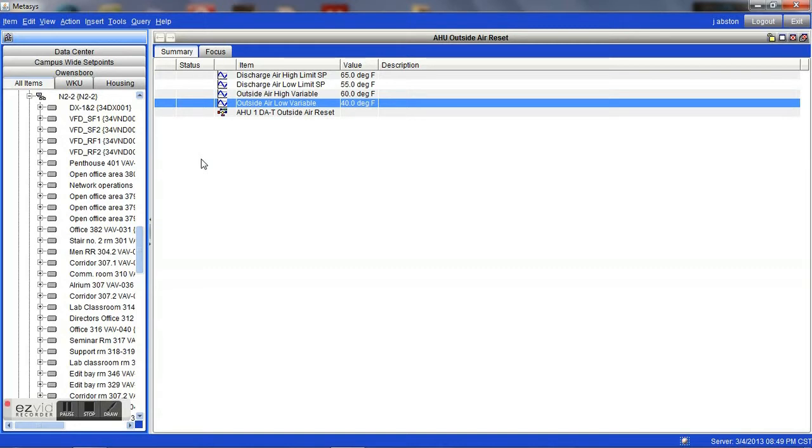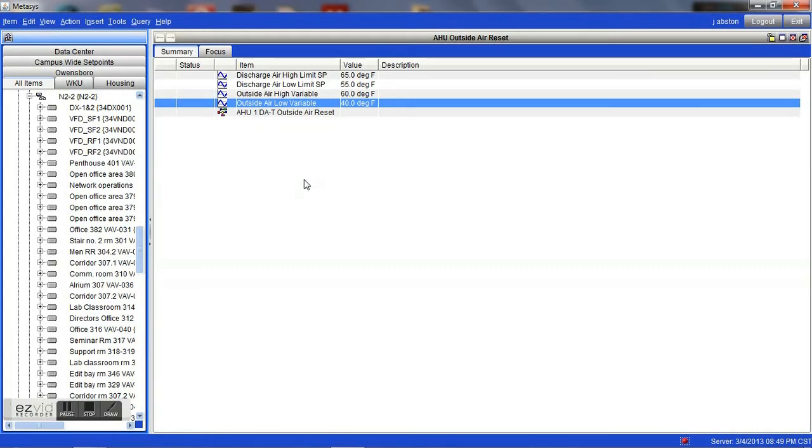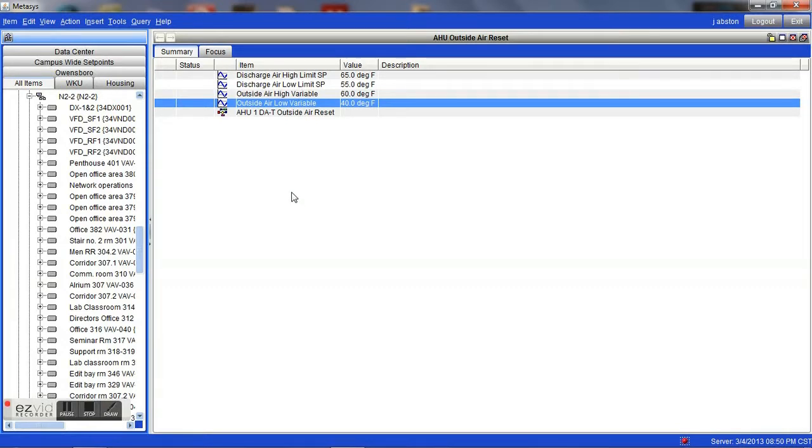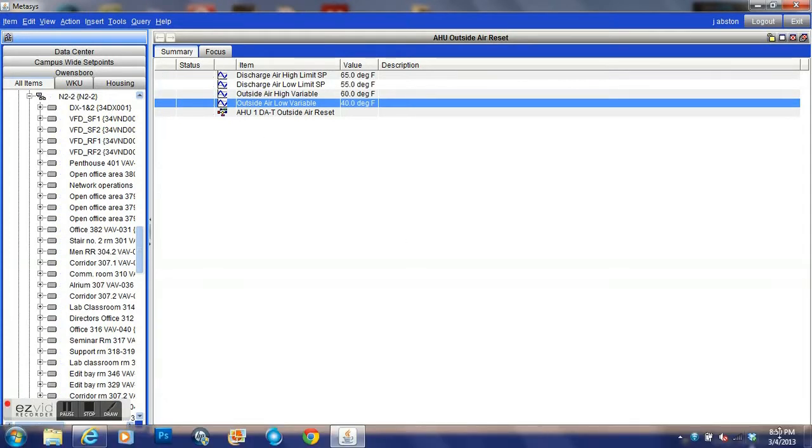As you know, the main discharge temperature of a large air handler will usually run cooler than what you may expect. That cooler air is used to cool down spaces throughout the building, and whenever a space is below set point, the air will be reheated within a particular zone through a VAV reheat system. Sometimes that is through hot water or even electric. In the winter months, it is not as critical to run a lower discharge temperature on an air handler as it is in the hotter summer months.